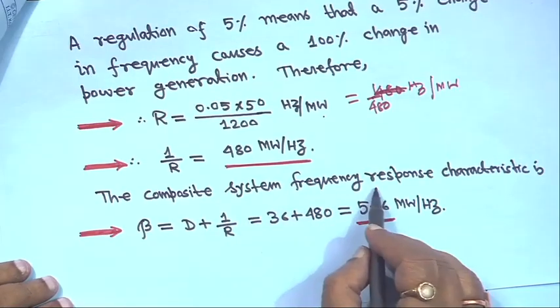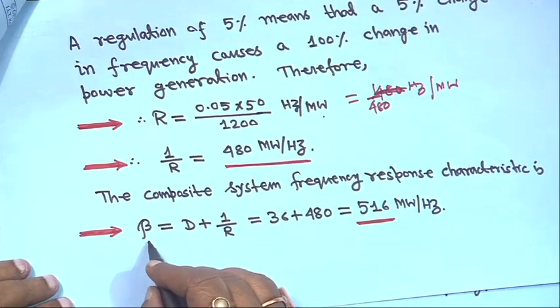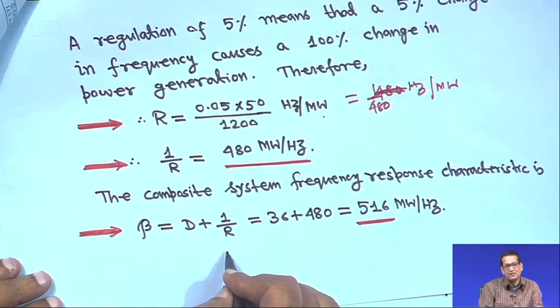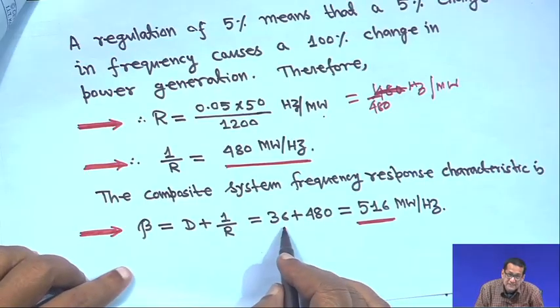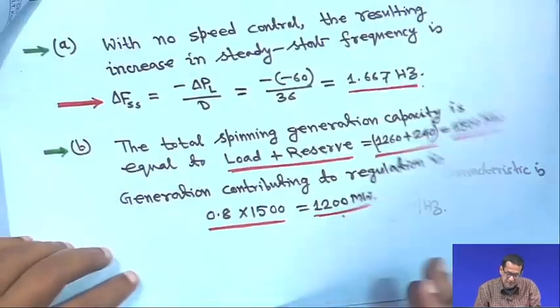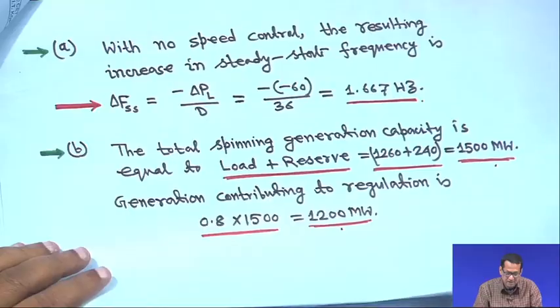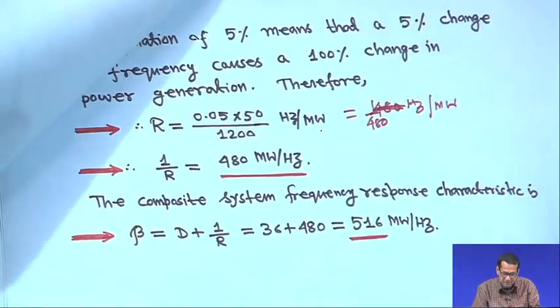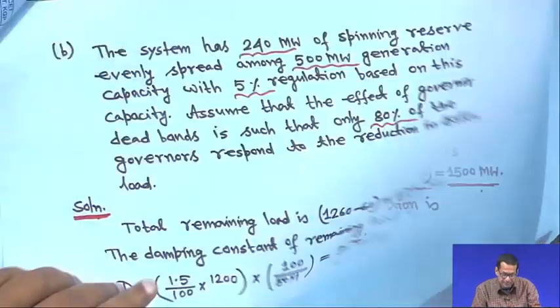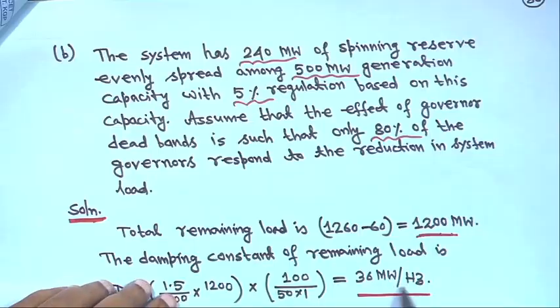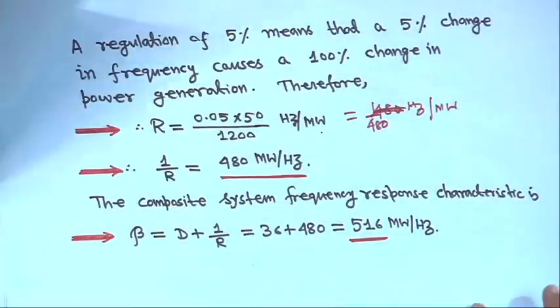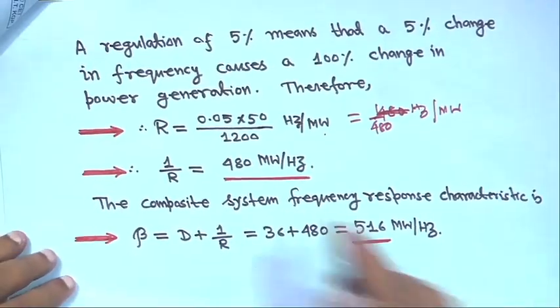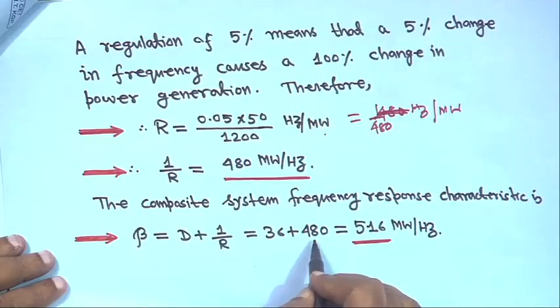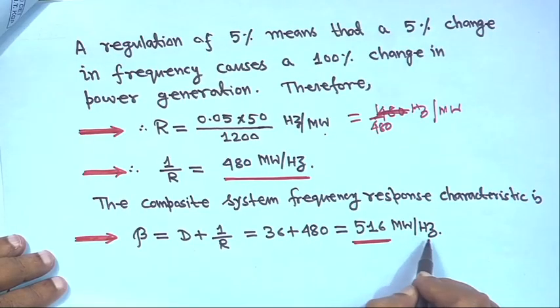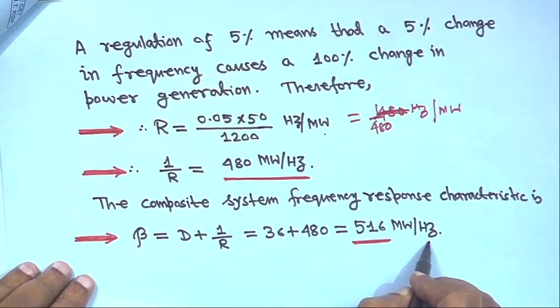Therefore the composite system frequency response characteristic, we know, beta is equal to D plus 1 upon R. D we computed just now as 36 megawatt per hertz, and 1 upon R is 480 megawatt per hertz. So 36 plus 480, so 516 megawatt per hertz is the composite system frequency response characteristic.